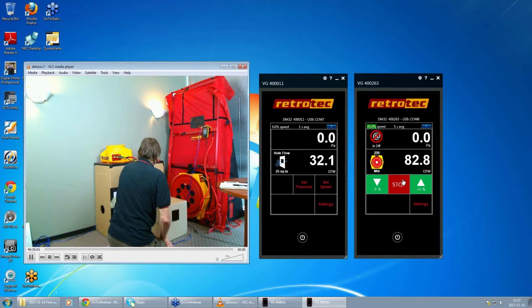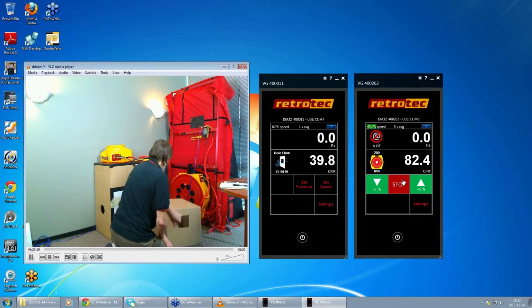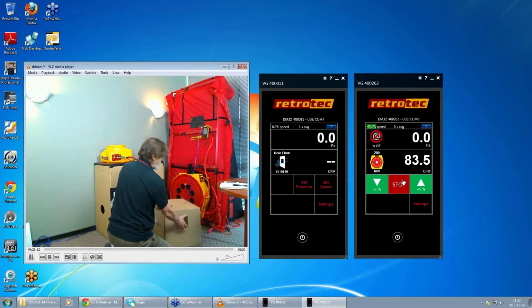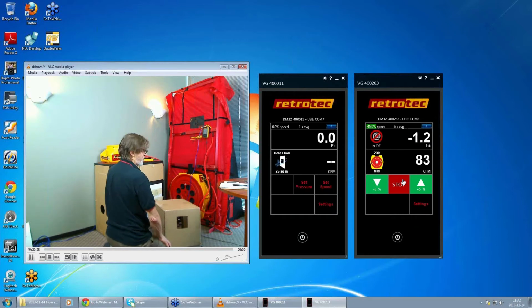Whenever you're doing one of these, something you have to bear in mind is that this hole has got to be relatively small compared to the holes that the air is going through. If this hole is tiny, then we get a lot of pressure across here. So typically with these boxes, if the duct pressures are low, you only want to get like 5, 10, at the most 15 pascals inside this box in order to continue to get accurate readings.